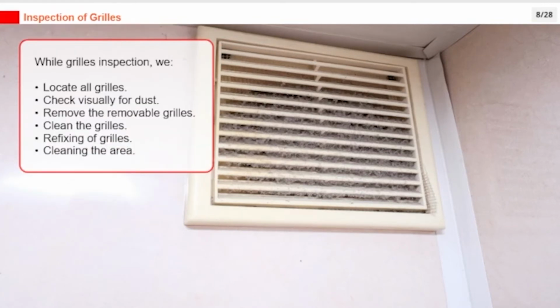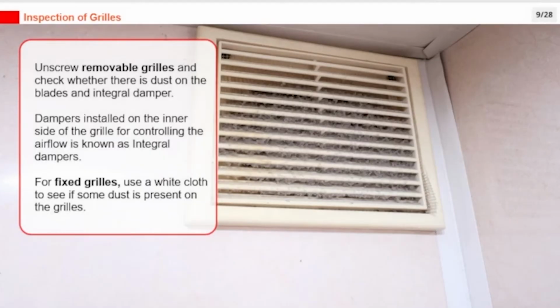While inspecting grills, we locate all grills. Check visually for dust. Remove the removable grills. Clean the grills. Refix the grills. Clean the area. Unscrew removable grills and check whether there is dust on the blades and integral damper. Dampers installed on the inner side of the grill for controlling the airflow are known as integral dampers. For fixed grills, use a white cloth to see if some dust is present on the grills.